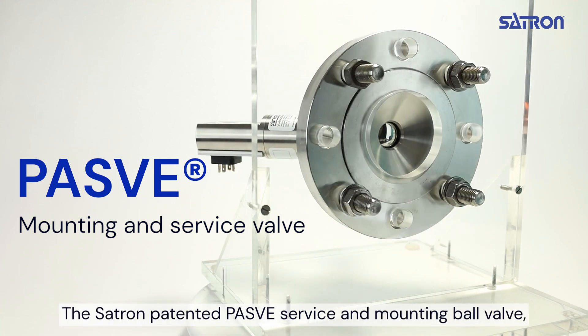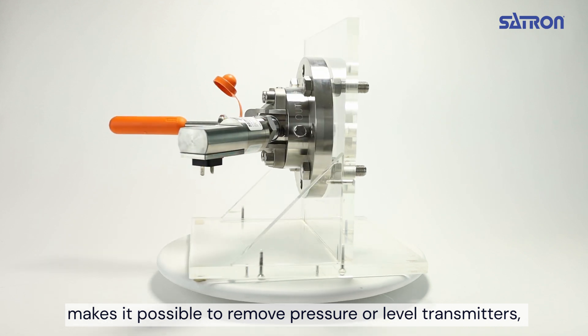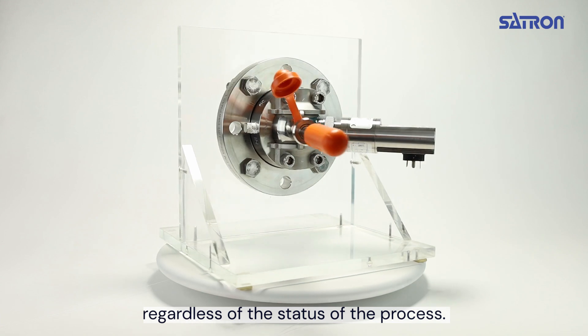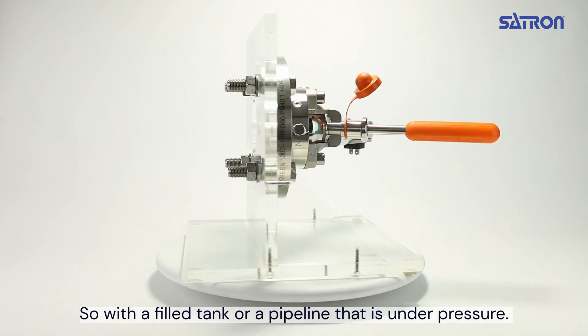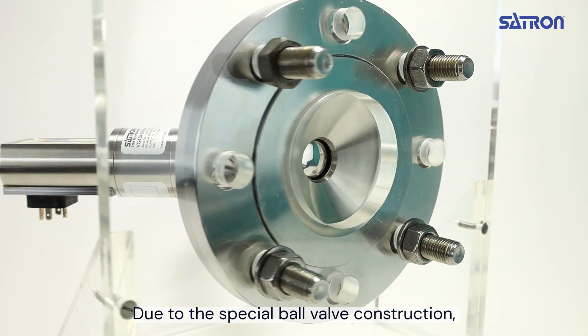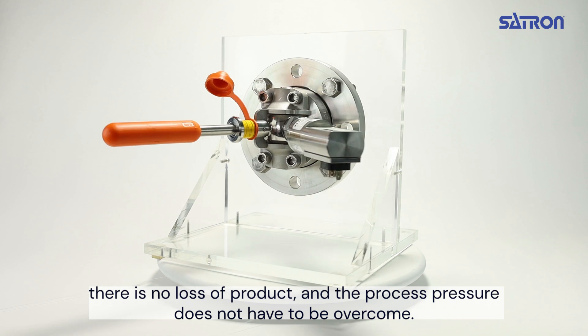The Satron patented PASVE service and mounting ball valve makes it possible to remove pressure or level transmitters, regardless of the status of the process — including a filled tank or a pipeline that's under pressure. Due to the special ball valve construction, there is no loss of product and the process pressure does not have to be overcome.